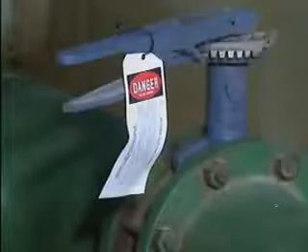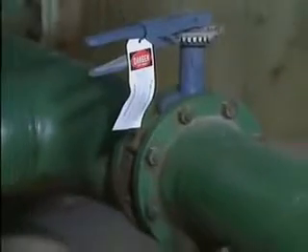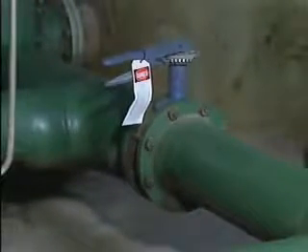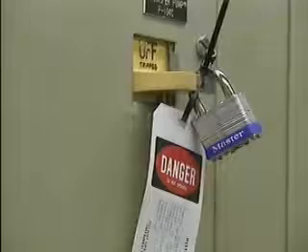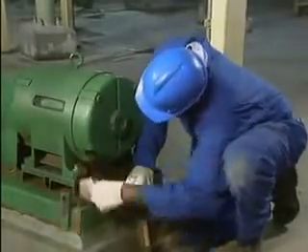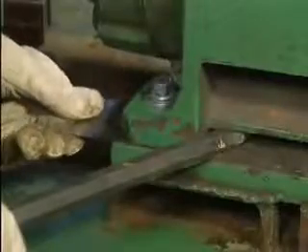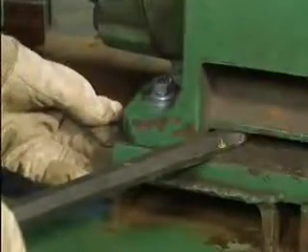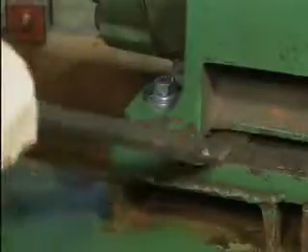The basic purpose of a shaft alignment is to make sure that the center lines of the shafts are as close as possible to being collinear. That is, that they form one continuous straight line. But before a shaft alignment is performed, certain preparations must be made. For example, since safety is always the top priority during any maintenance undertaking, all applicable lockout-tagout procedures must be followed. Also, the equipment being aligned must be cleaned and inspected, and any conditions that could interfere with the shaft alignment, such as soft foot, must be corrected.